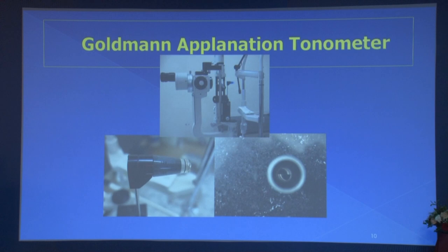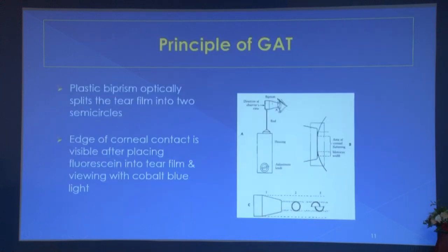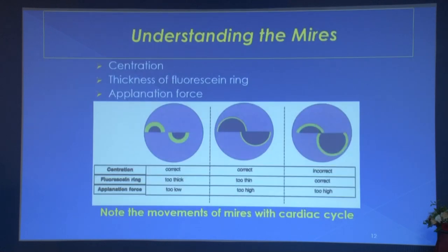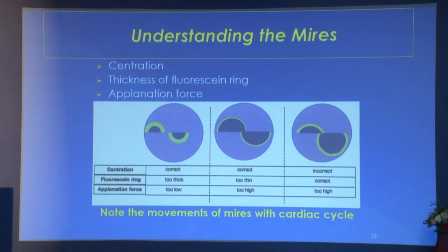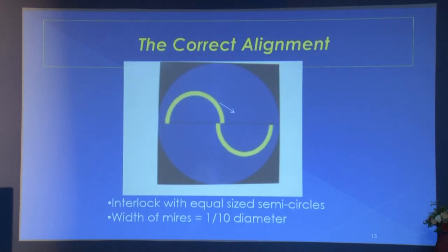The Goldmann applanation tonometer uses a plastic biprism that optically splits the tear film into two semicircles. The edge of corneal contact is visible after placing fluorescein in the tear film and viewing with cobalt blue light. Correct alignment requires the two semicircles to interlock with equal size and width — the mires width should be one tenth of the total diameter.